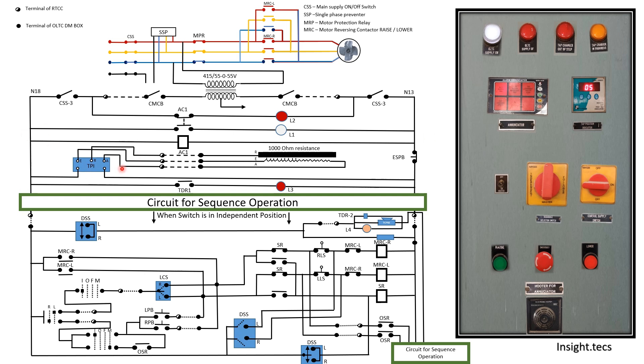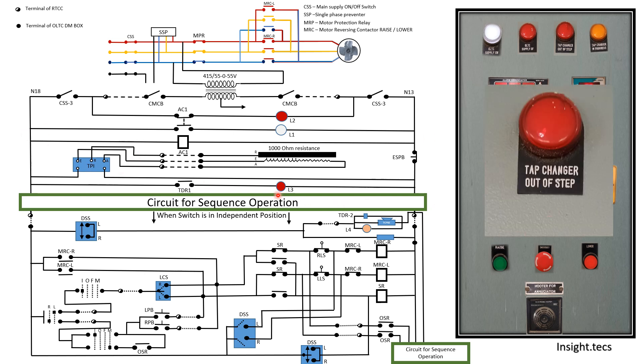Next is the tap changer out-of-step LED, L3. Whenever you are changing the tap position and the process is in between — whenever the tap position is not completely changed — at that point the L3 LED will glow. It glows using the contact of TDR1. We will learn in more detail about TDR1 later.